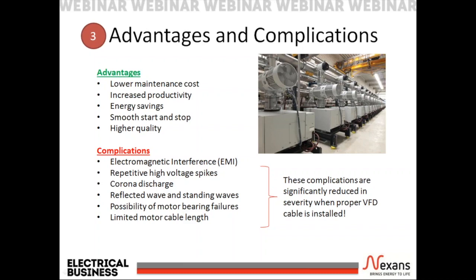The complications experienced with VFDs are significantly reduced in severity when proper VFD cables are installed. These complications include electromagnetic interference, or EMI. Outbound or inbound interference may cause issues with the VFD system, external wireless or even wired systems for that matter. Repetitive high voltage spikes. It is normal for these voltage spikes to reach 3.1 times nominal system voltage rating. Corona discharge, which could ultimately lead to conductor insulation failure.